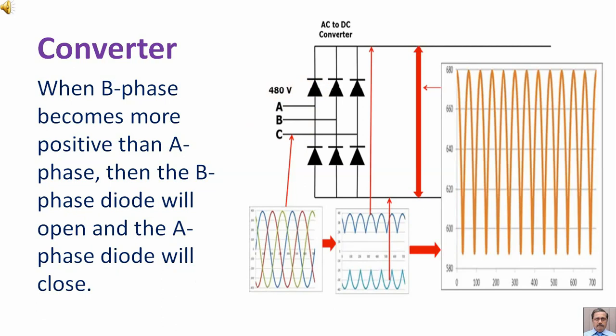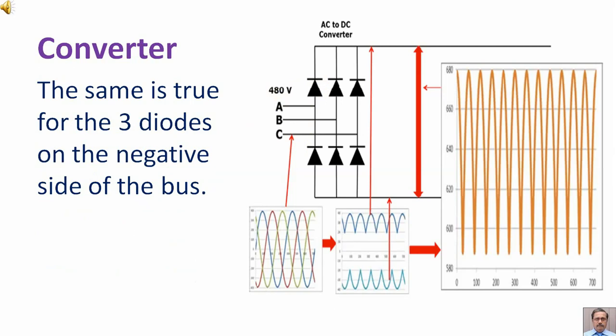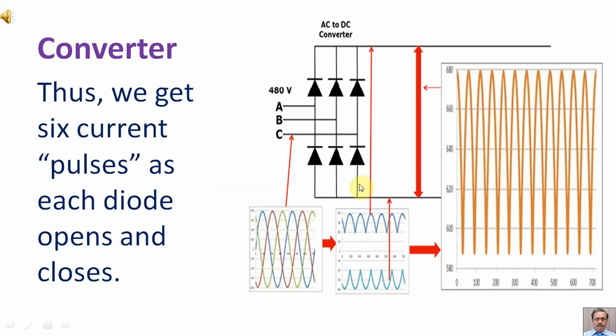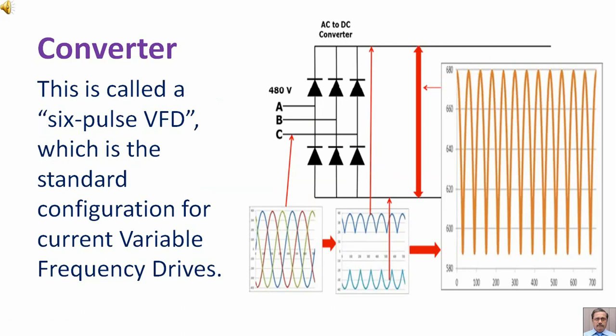When B phase becomes more positive than A phase, then the B phase diode will open and the A phase diode will close. The same is true for the three diodes on the negative side of the bus. Thus we get six current pulses as each diode opens and closes. This is called a six pulse VFD, which is the standard configuration for current variable frequency drives.